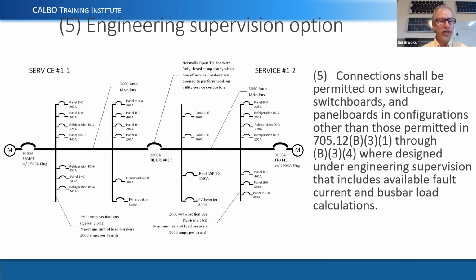Okay, so engineering supervision, that's one of those areas where I'd like to see a lot more people using this particular provision. And that's where, when we have large switchgear, 3,000 amp, 4,000 amp switchgear, 2,000 amp switchgear, any loads that we put in a panel like that are done under engineering supervision. And then if we're particular about where we put our PV inverters and installing them on there, we can show through fault analysis that there's no way, there's no physical possible way, even if all the circuits were off or all the circuits were on or any weird combination thereof, there's no way to overcurrent anything in this equipment. Engineer can do those calculations very well and very easily. And so the 120% rule does not apply whatsoever.